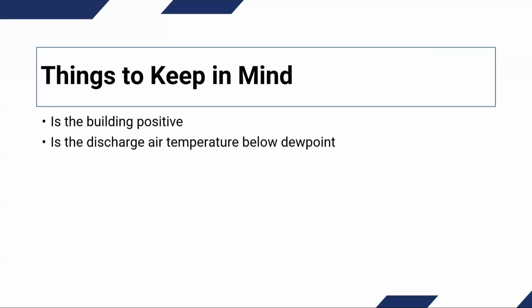So the other thing that I've brought up multiple times, I had a couple of slides that had the psychrometric chart. We use the psychrometric chart a lot when we're evaluating buildings. It really helps us to see if we're removing the moisture, or if we're not removing the moisture. But the next key is, are we reaching dew point? So is the discharge temperature of the unit going to dew point?